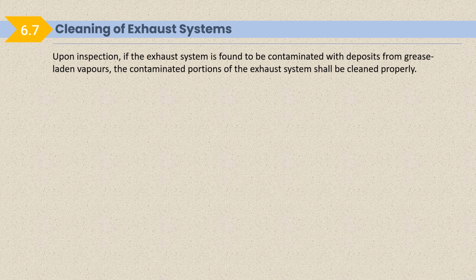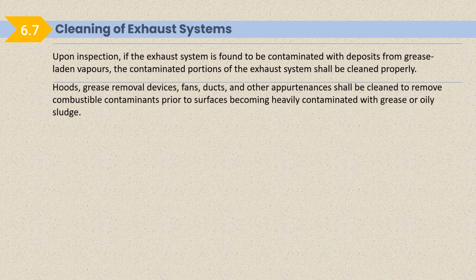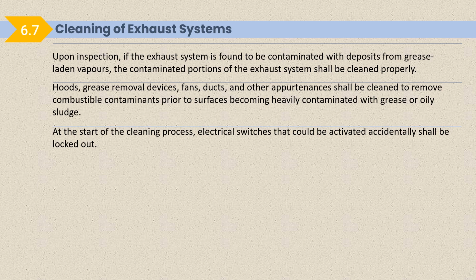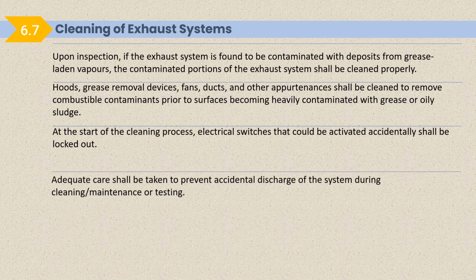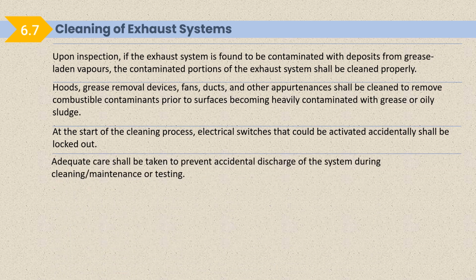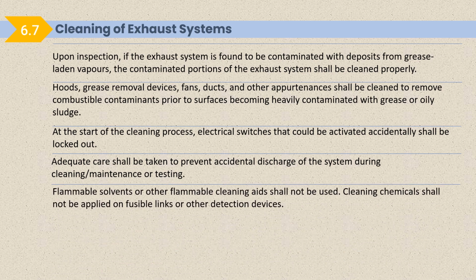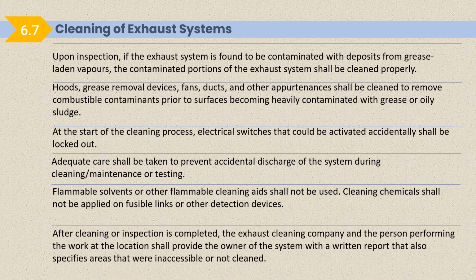Cleaning of exhaust system. Upon inspection, if the exhaust system is found to be contaminated with deposits from grease laden vapors, the contaminated portion of that exhaust system shall be cleaned properly. Hood, grease removal devices, fans, ducts and other appendages shall be cleaned to remove combustible contaminants prior to surfaces becoming heavily contaminated with grease or oily sludge. At the start of the cleaning process, electrical switches that could be activated accidentally shall be locked out. Adequate care shall be taken to prevent accidental discharge of the system during cleaning, maintenance or testing. Flammable solvent or other flammable cleaning aids shall not be used. No flammable solvent shall be used for cleaning purposes. Cleaning chemicals shall not be applied on fusible links or other detection devices.